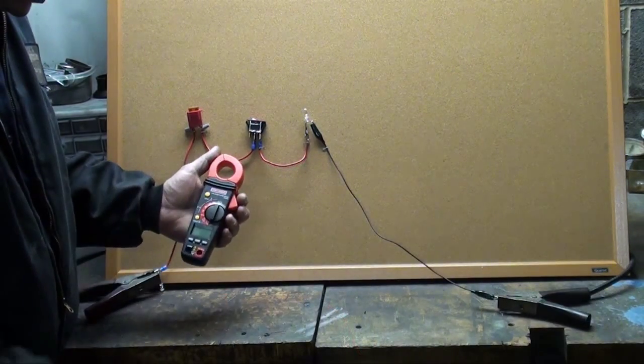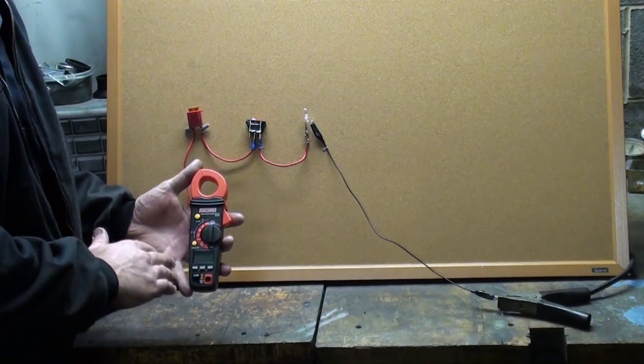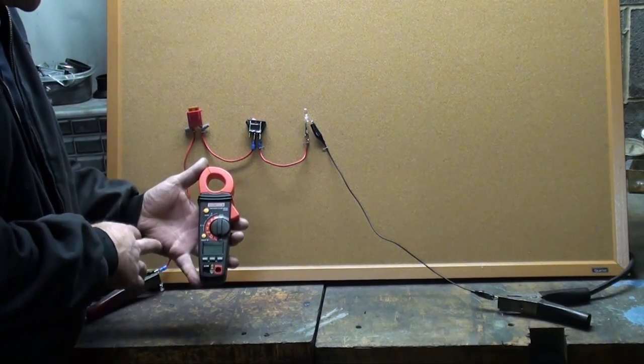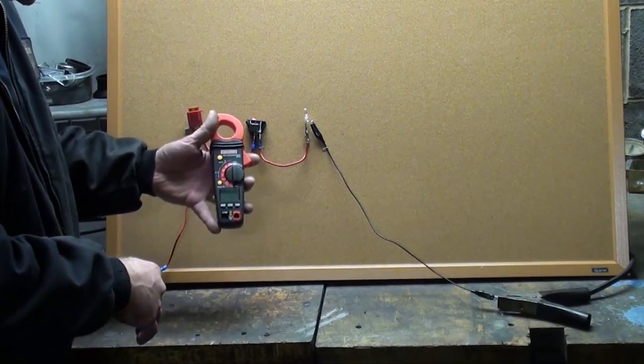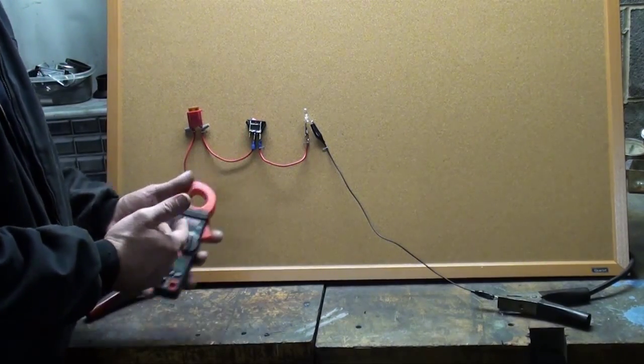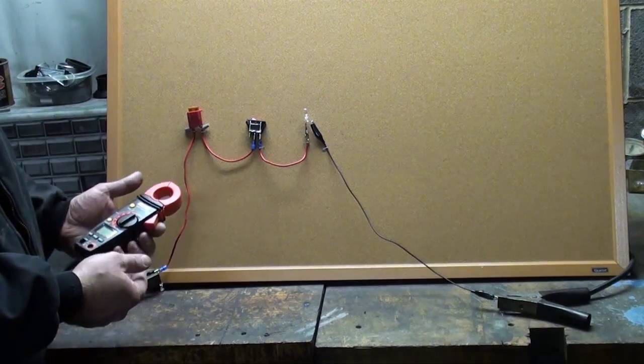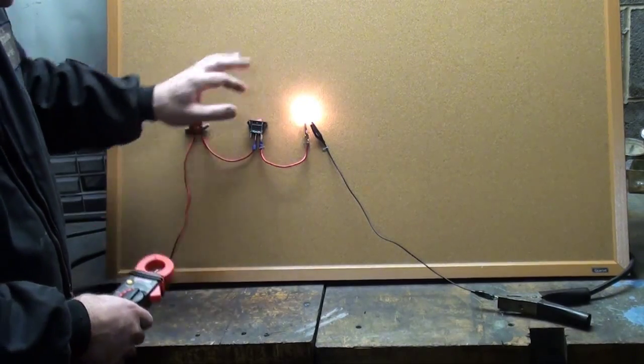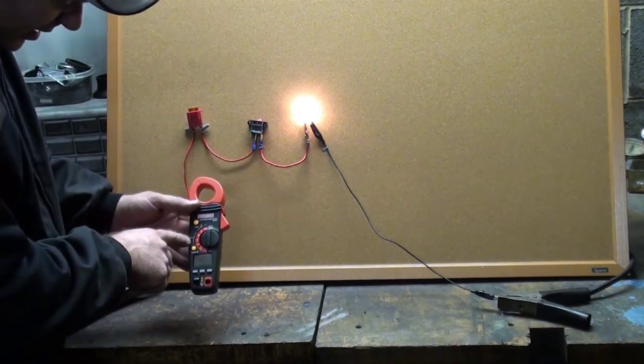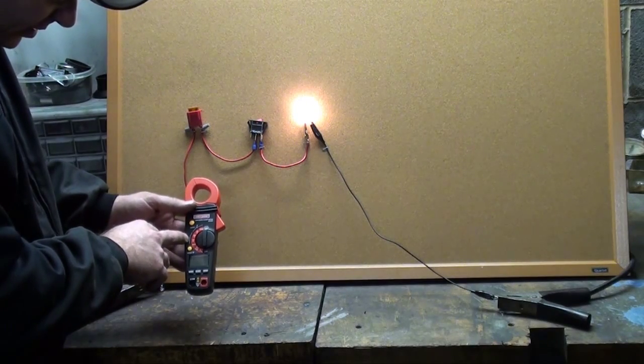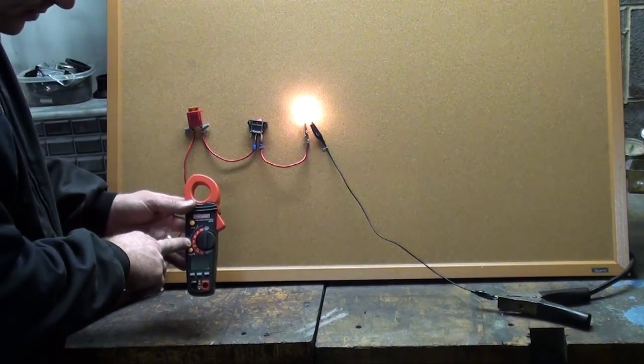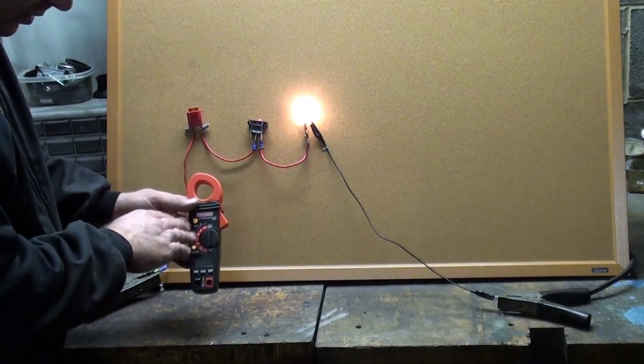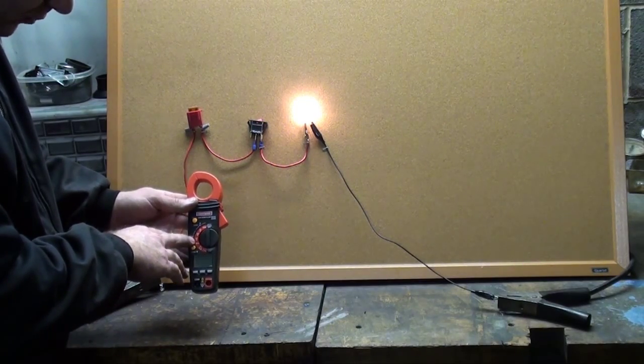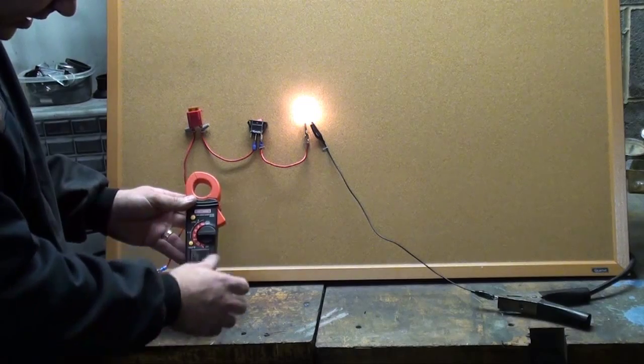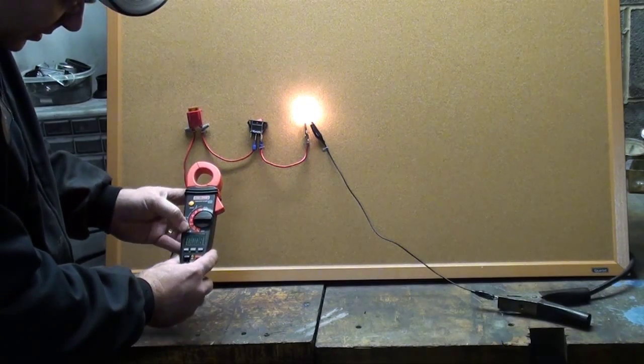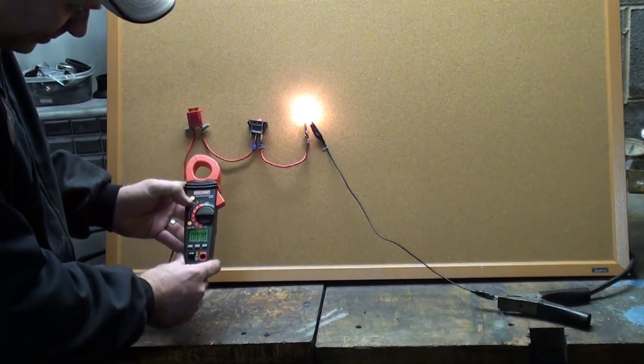And that brings us to the clamp ammeter. What's nice about the clamp ammeter, like I mentioned in the previous video, is that you can simply clamp it around the conductor without opening the circuit or finding an open. You power up the circuit and set it to your DC amps. The lowest scale is 40 amps on this one, the highest is 400. I'm way under 400, under 40, so I'll set it to the 40 amp scale. Let me turn the backlight on for you.